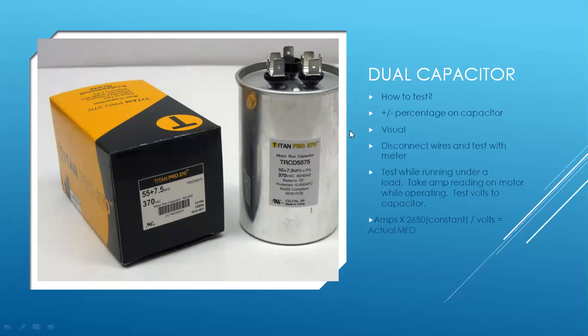The big question is how to test. Two ways you can test it. One is to power down the unit, pull the wires off, discharge your capacitor, and then do a microfarad check on it. So this one here, for instance, it's saying 55, 7.5, 370 with a plus or minus 5%. So if it's 55 or 7.5 and it's below 5%, it's below the allowable capacity. That's going to cause extra load on your compressor, extra load on your fan motor. So if it's low, you can use this label right here to show the customer, and you can do it right in front of them to sell that. So if it's below the allowable percentage, recommend replacement.